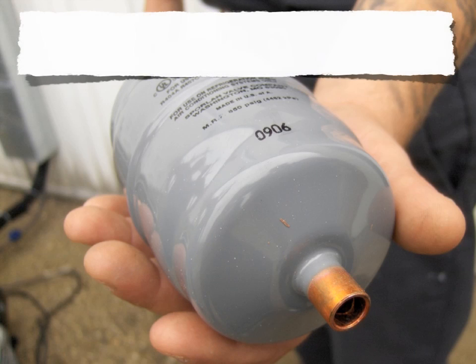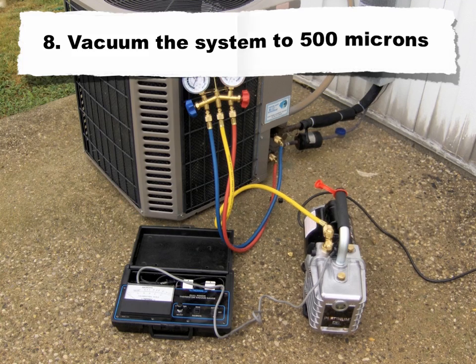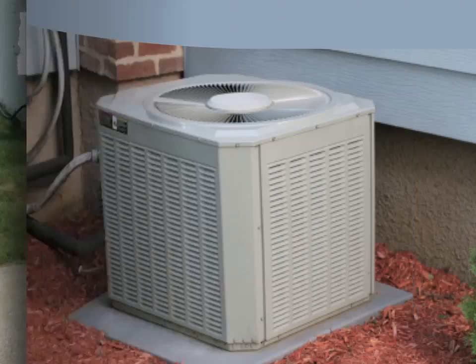6. Replace the TXV, if required. 7. Replace all refrigerant filter dryers. 8. Vacuum the system to 500 microns. 9. Recharge the system with R-422B to 95% of the original R22 weight. Don't charge by sight glass, as it could lead to an overcharge. 10. Start the equipment and run for 30 to 45 minutes for the system to stabilize.